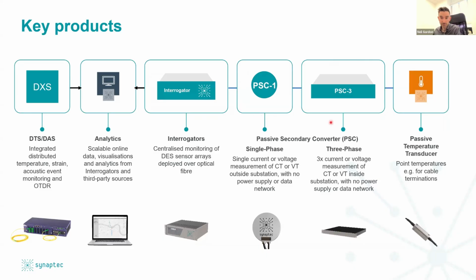Our electrical sensors for current and voltage are captured by these devices called passive secondary converters, literally because they are passive at the measurement location. They have no active electronics, require no power supply, and they convert the secondary of a standard instrument transformer into an optical measurement. These come in 2 flavors. I'll come to these in a bit more detail on the next slide, but you have the PSC1, which is our ruggedized remote outdoor single-phase measurement, and the PSC3, which is designed as a 3-phase measurement unit to deploy in the substation in the protection and control rack, for instance, and really is typically used to retrofit to the secondaries of an existing CT in the substation yard, so you don't have to install new CTs at that location.